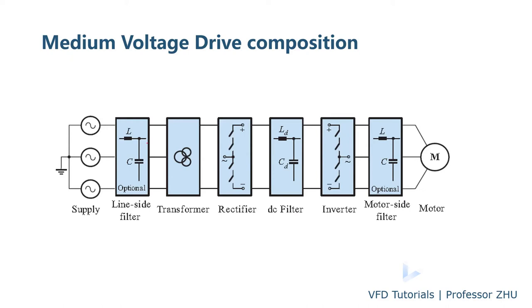This is a typical composition of a medium voltage drive. We have the rectifier, which converts AC to DC, and a DC filter using a capacitor or reactor. Then the inverter, DC to AC. And sometimes on the motor side you have a filter. Also, most of the medium voltage drive has a transformer on the input side. And sometimes you need a line-side filter. And here is the power supply.